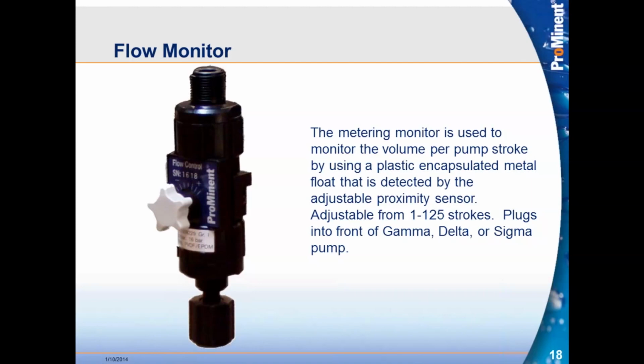However, what you can do, and we could do that for you with our panel shop, is we can have it open the pause contact on the universal control cable. So we would open the connection between the black and brown wire, so the pump goes into a pause mode briefly. Then we reconnect that, we short those back together so the pump comes out of the pause and it goes back to run. So when we recycle that pause contact, it starts the pump over and resets that 125 number. So now we're going to run another 125 consecutive strokes before we go into a fault again.